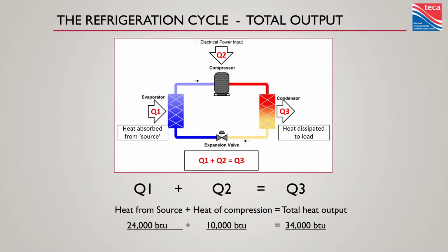Common, this is not a hard and fast, every heat pump works like this moment, because you're going to see these things are dynamic, but a common analogy would be absorbing 24,000 BTUs from the outside air, using 10,000 BTUs of electrical energy to deliver 34,000 BTUs of heat energy. So we only paid for that 10,000. We got that 24,000 from outside, we delivered 34,000. So that would be 340% efficient, COP at 3.4.